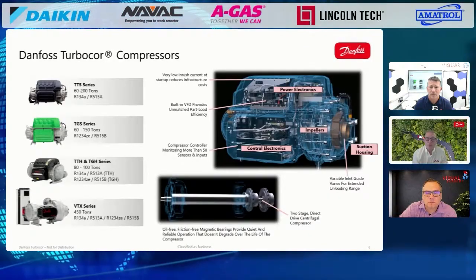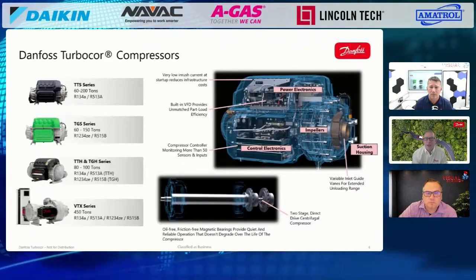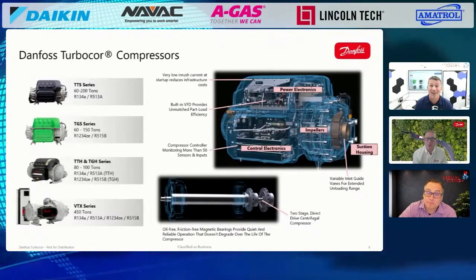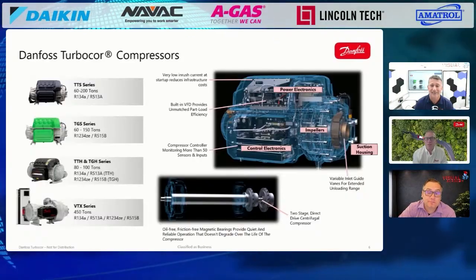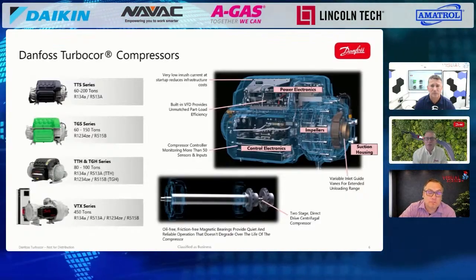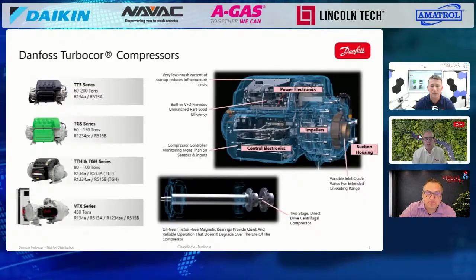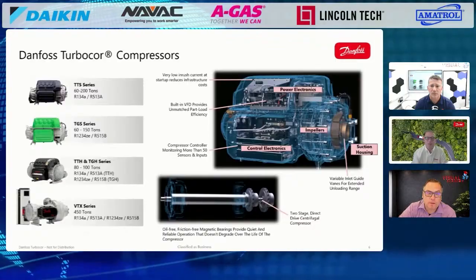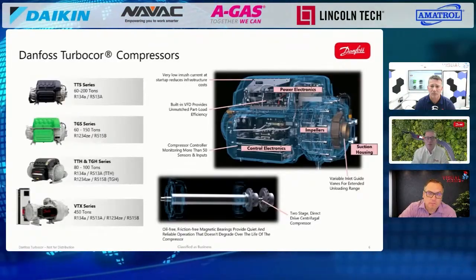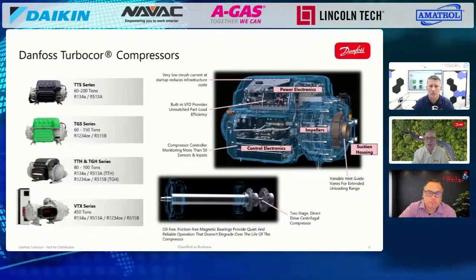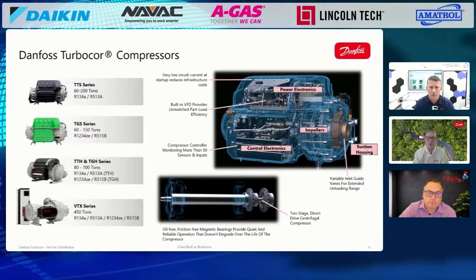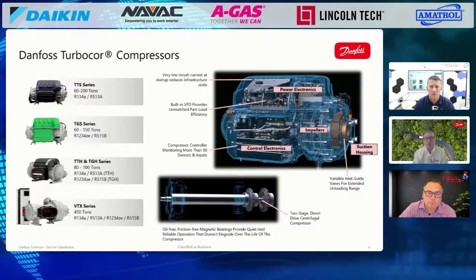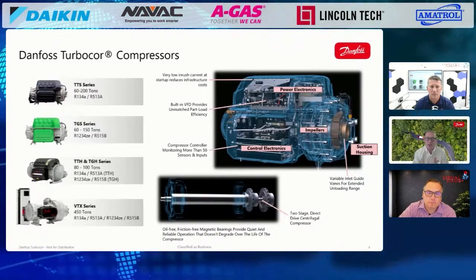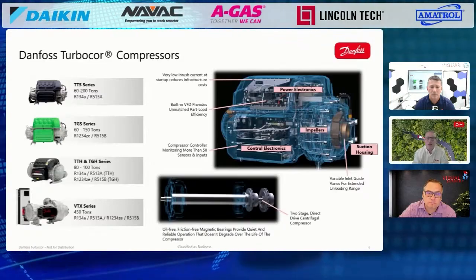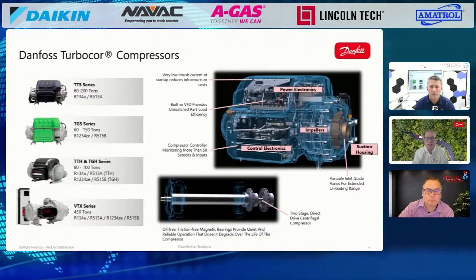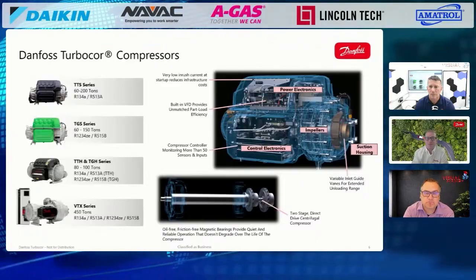Yeah, it's full variable speed. So we can unload down to, depending on the compressor model, somewhere between 10 and 20% of the compressor full capacity. So some significant unloading, especially since these are larger capacity models. Historically, we'll see single or maybe 2 compressor chiller designs. But now, especially with these data centers, we're seeing larger and larger capacity chillers, so you're putting multiple compressors on there. So you can really unload very, very low, but then still have the full capacity to ramp up and get that full load.